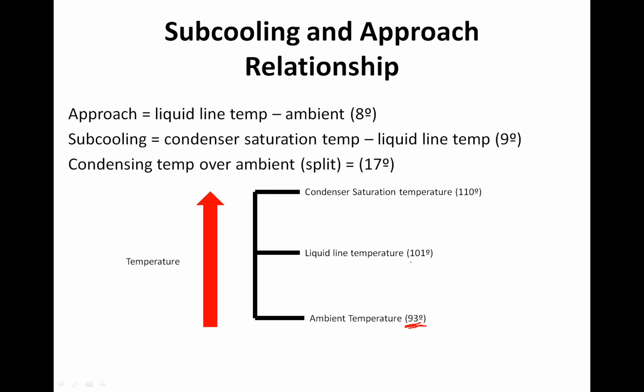Like you may have an issue where the condenser's got a restriction in it. Sometimes they put liquid line filter dryers in the condenser, and you'll be going out there measuring, the outdoor air temperature is 93, and all of a sudden your liquid line temperature is 90. Well, how's that possible, right? Because the condenser is rejecting the heat, and the air is what's cooling the condenser. So the coldest the liquid could get is the same as the ambient air temperature. If you drop below that, you've got a restriction in there, and that's covered in our guide on troubleshooting refrigeration systems. There's a guide online. I'll show you when we're done.